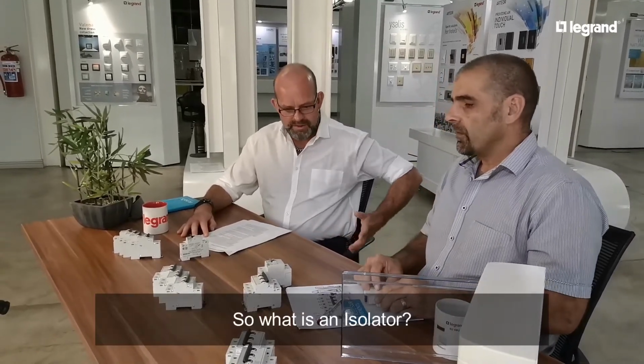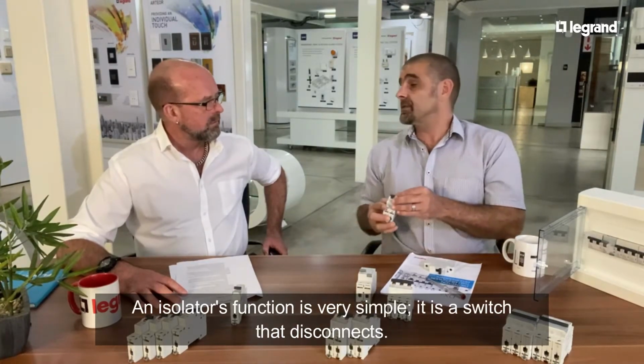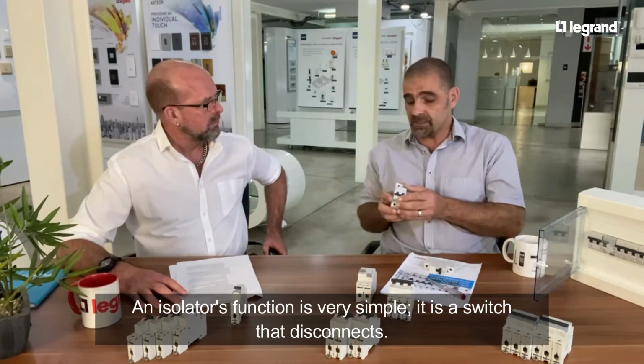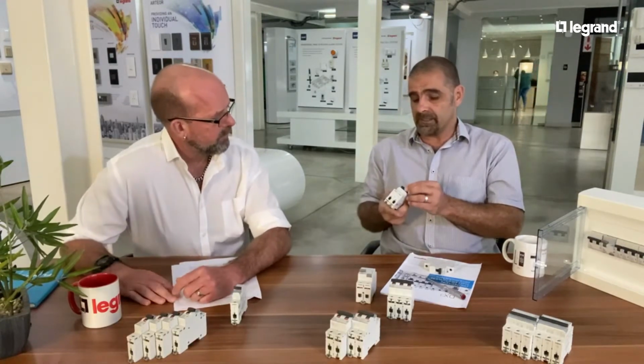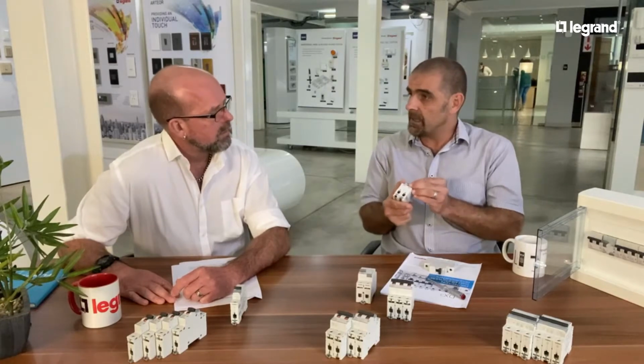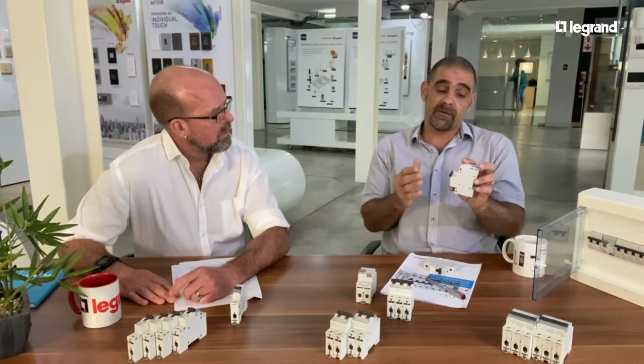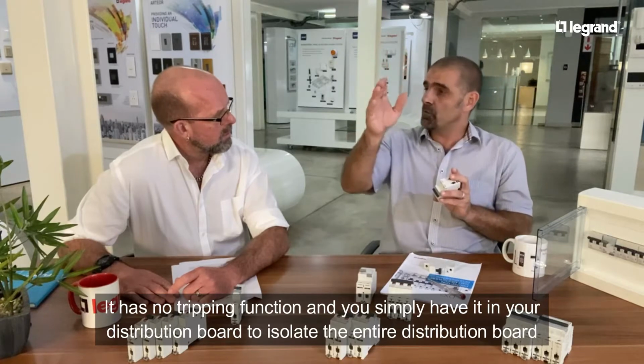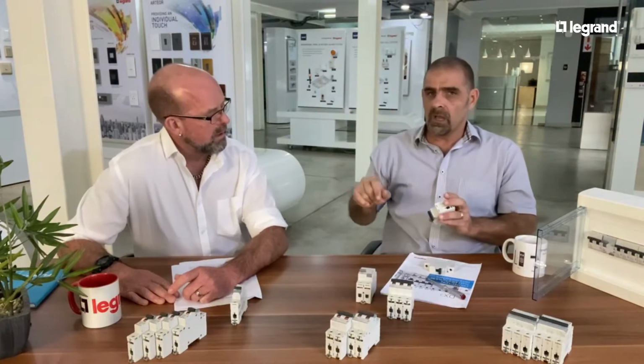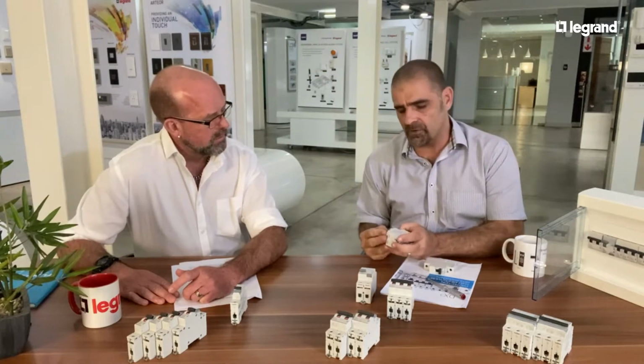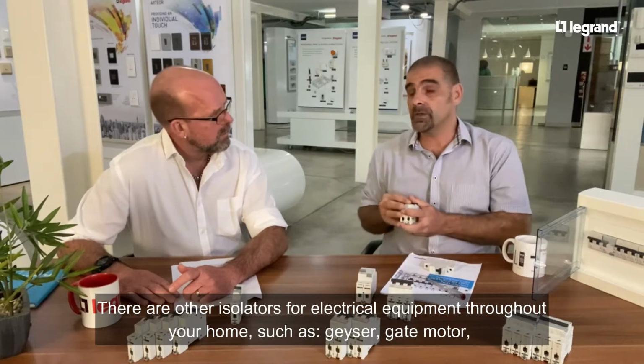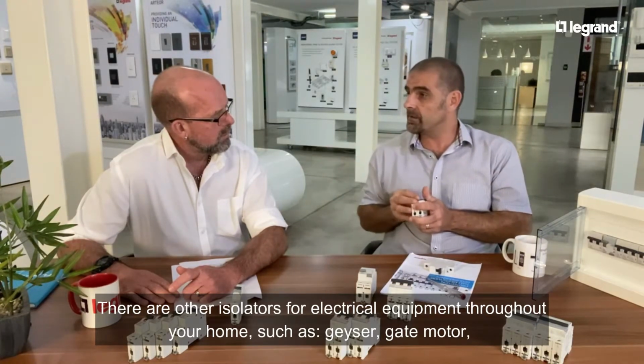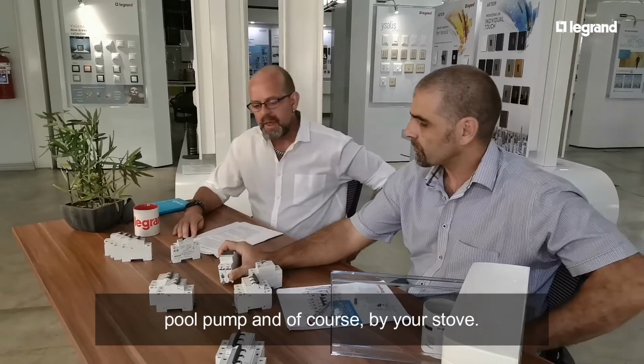Okay, so now moving on to an isolator, what is that? An isolator's function is very simple. It just disconnects. It's a switch. So it disconnects your power. There's no tripping function, and you can have the isolator, for example, at your distribution board to isolate the entire distribution board. There are other isolators throughout your home. You will find them at your geyser, your pool pump, gate motor, and as well as your stove, you'll have an isolator there.